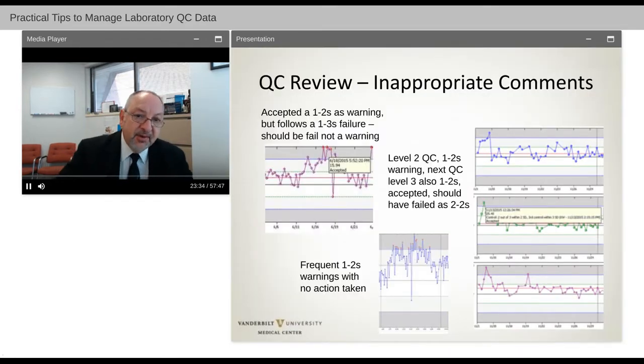Now, we also look for incorrect comments and incorrect troubleshooting comments from our techs, where they have accepted out of range QC when it should have been a failure and they should have troubleshot this, such as accepting a 1-2S warning, but it's actually a 2-2S because it followed a 1-3S. So it is outside of 2S successively. Frequent 1-2S warnings with no action is an issue, as it shows that we may have had a shift in that QC close to being out of range, and the tech will accept it when it's in range, but the very next analysis of that QC, it's out of range and they're troubleshooting again. This means we really should be troubleshooting system performance and not just trying to squeak the QC back in.